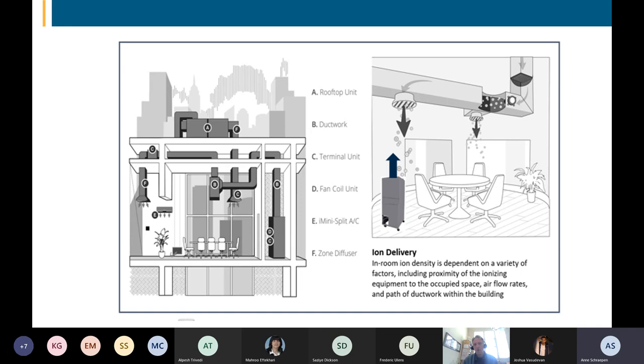Bipolar ionization technology or others that I've mentioned can typically be installed in traditional HVAC systems almost anywhere. So starting in the space, perhaps in a HEPA filtration machine that's been wheeled into the space, perhaps in the ductwork adjacent to the space, perhaps further back in the ductwork, perhaps inside a furnace or a fan coil or a small air handling unit, perhaps inside of a VAV box, perhaps inside of a mini split or a VRF fan coil unit indoors, or perhaps on the roof or in the basement in larger packaged rooftop units or built up air handling unit systems.